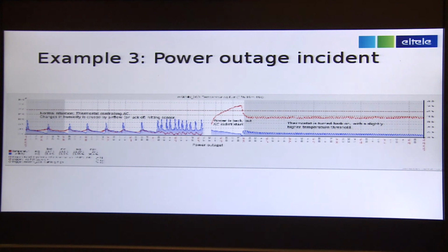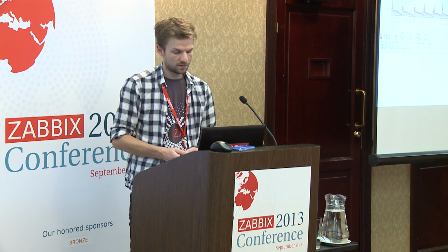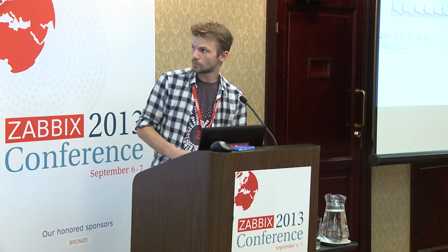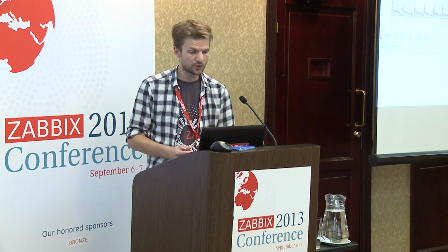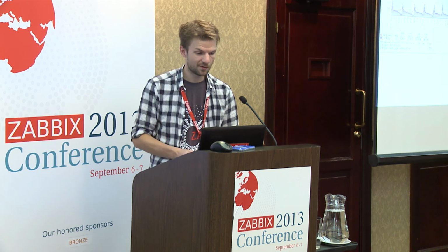Then we come into the middle. We have that nasty gap that none of us likes. It just stops responding. Got an alarm, sensor offline. Okay, but we didn't really have time to react before it started answering again. And the graphing continued. Humidity went down. Temperature went way up. Eventually it hit the threshold and sent us an alert.